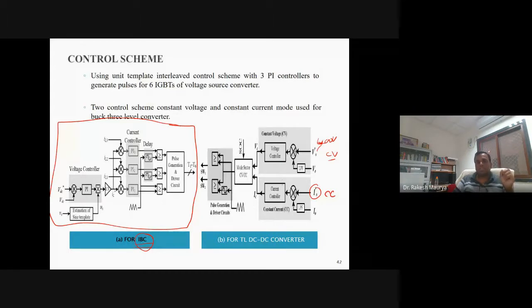So there are two independent loops: one is the CV mode controller, constant voltage controller, and the other is the CC converter, constant current controller. These two signals are available, and whether you select this signal or that signal depends on the state of charge, SOC, of the battery. Accordingly, pulses are given to switch 1 and switch 2. This is the control diagram of the TL DC-DC converter.